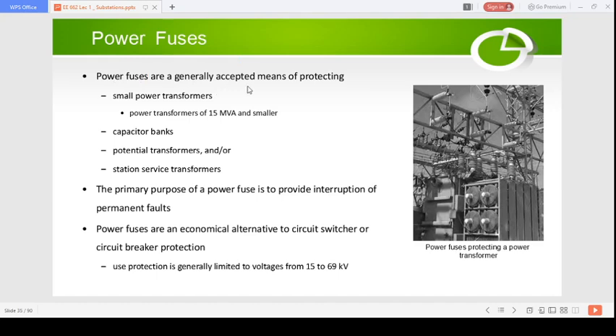Another type of device that you can find in a substation is called the power fuse. Power fuses are generally accepted means of protecting small power transformers. They are basically used to protect small power transformers which are 15 MVA and smaller. They can also be used to protect capacitor banks, potential transformers and station service transformers. So basically protection of small power transformers and other types of transformers, as well as the capacitor banks in the substation.